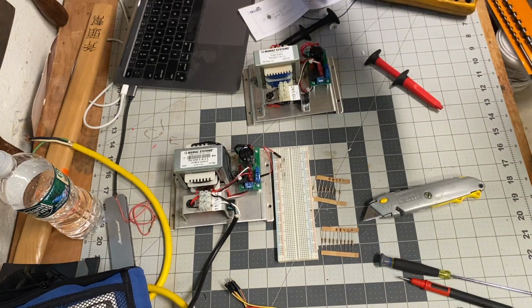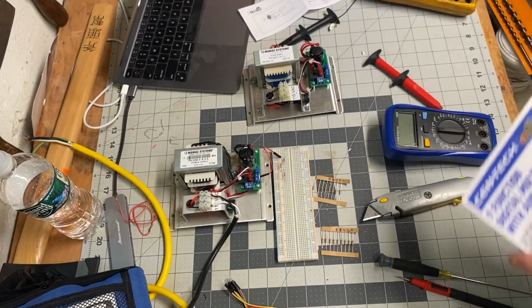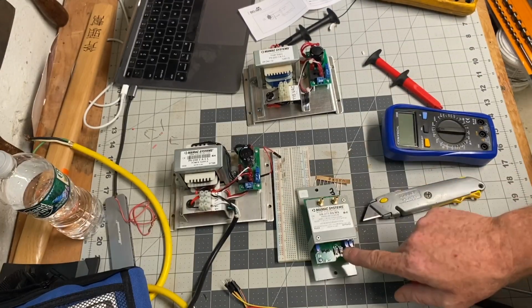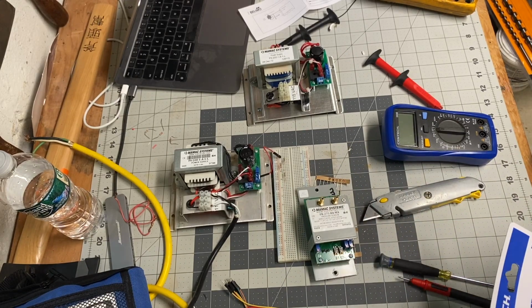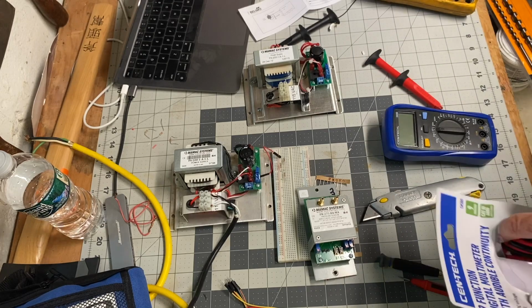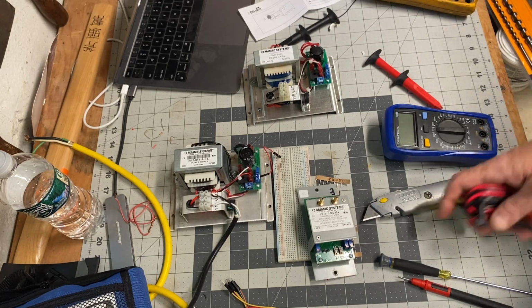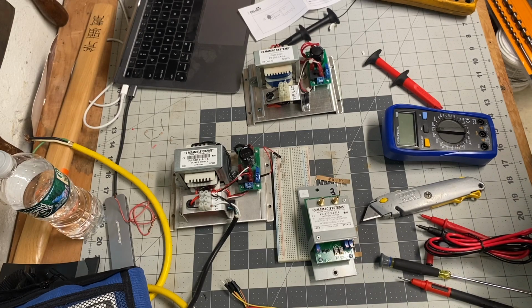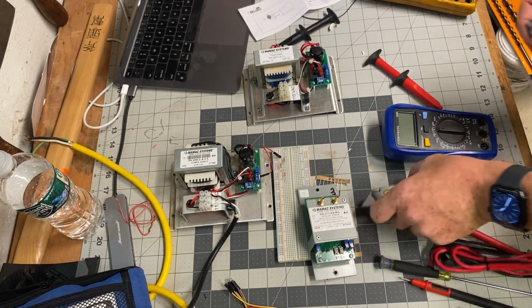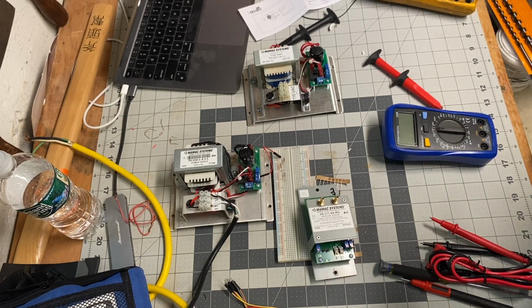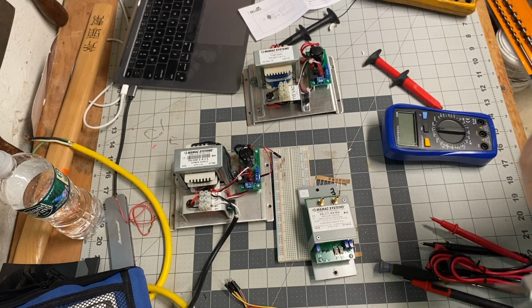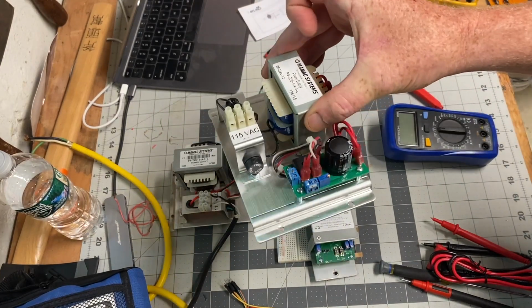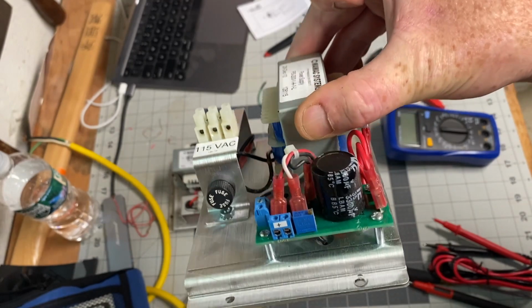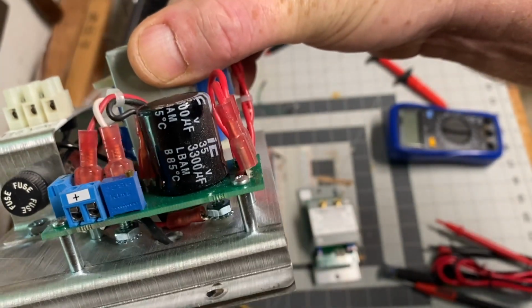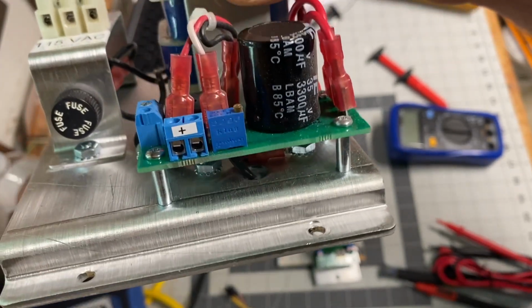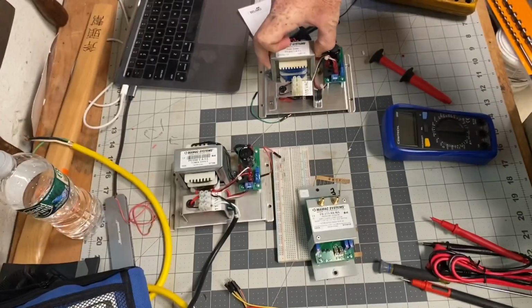After the guy had replaced the DP sensor but hadn't checked the voltage reading, positive and negative, to see if he had 24 volts. Ultimately, after finding out that the new sensor didn't work, checked the voltage, and it was reading about 19 volts DC instead of 24. So this transformer is putting out about 19 volts. And if you can see, the capacitor is bulged at the top just a little bit. And I'm guessing the capacitor is gone.